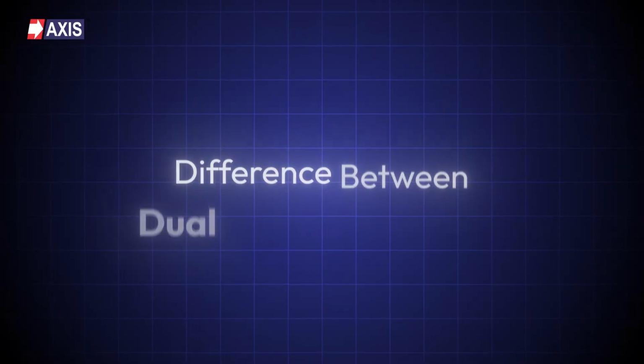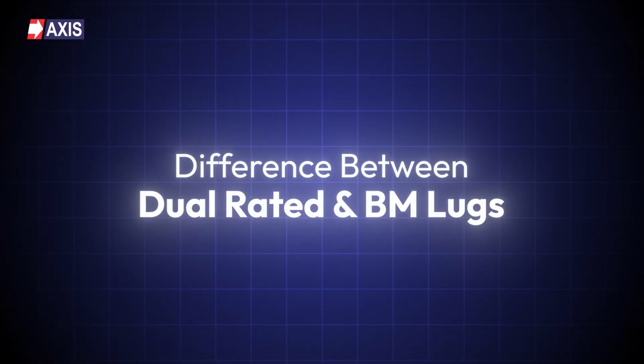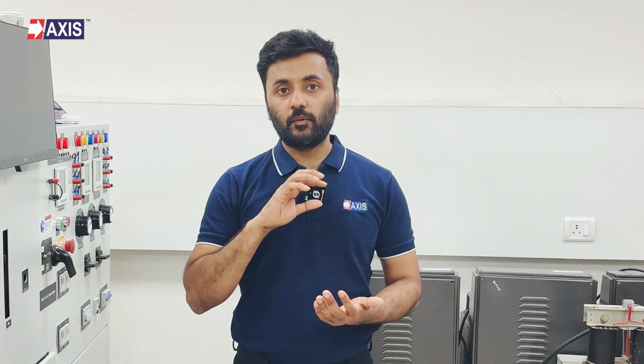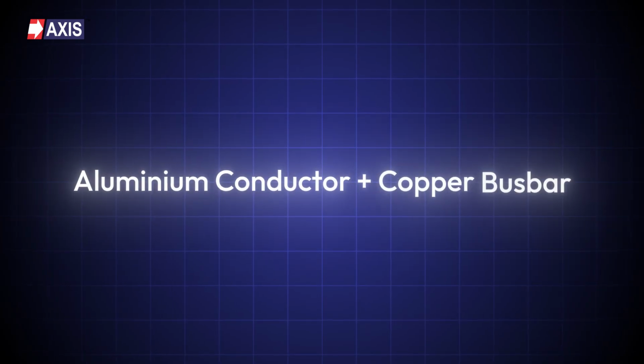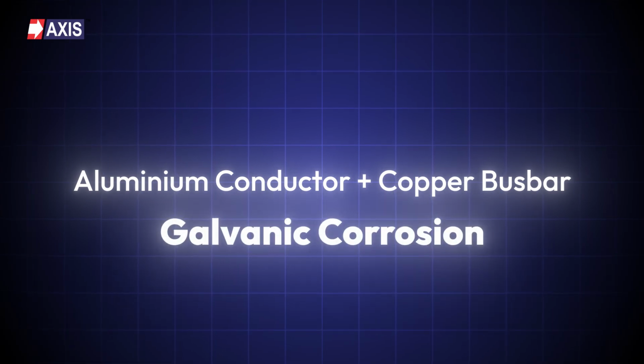Next, let's understand the core difference. A dual-rated lug gives you a choice. You can insert a copper conductor or an aluminium conductor into the same lug. So, if you use a dual-rated lug with an aluminium conductor and bolt it onto a copper bus bar, aluminium touches copper at the bus bar. Two different metals come in contact. Over time, moisture triggers an electrochemical reaction between them. This is galvanic corrosion.